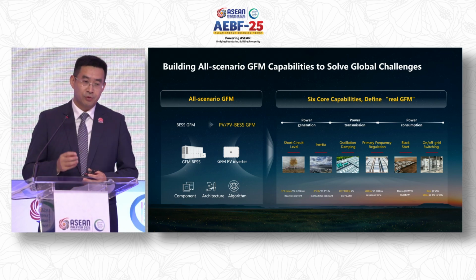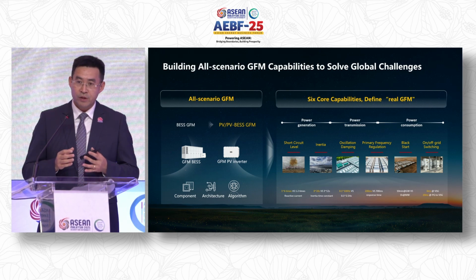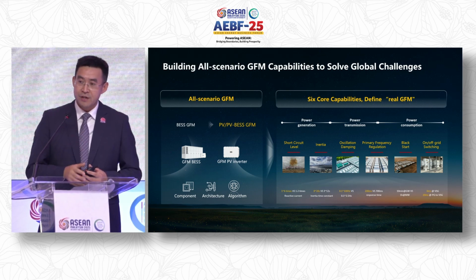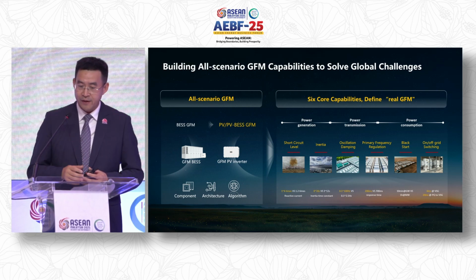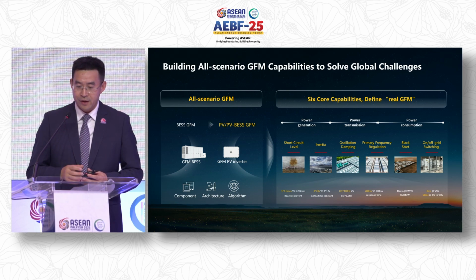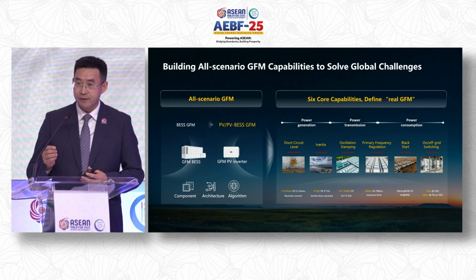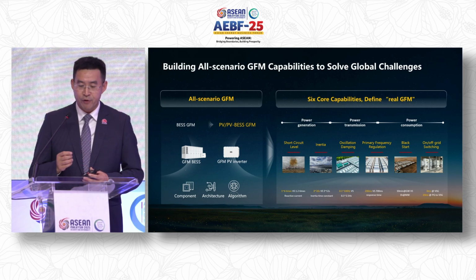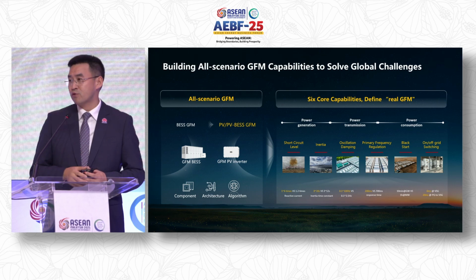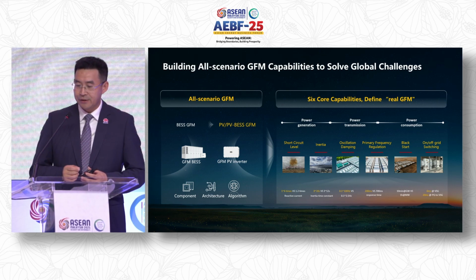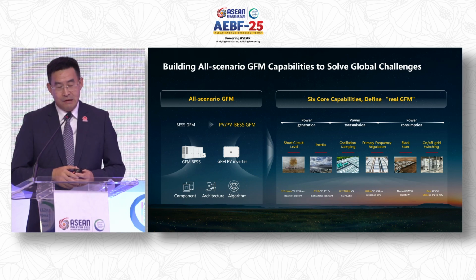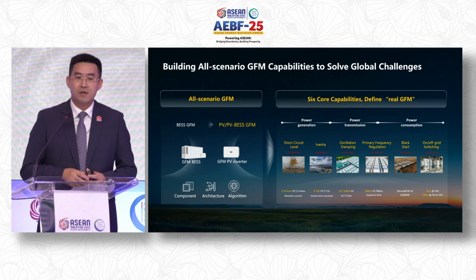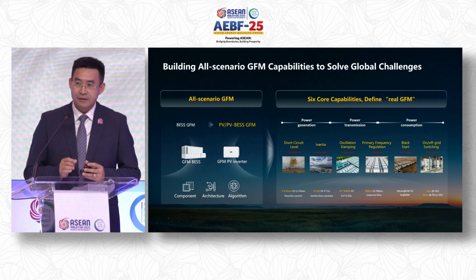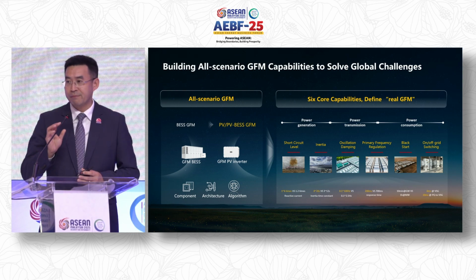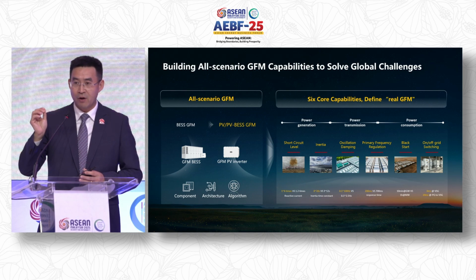Today we still want to emphasize that we define grid forming technology in 6 dimensions: first, short circuit level; second, inertia; third, oscillation damping; fourth, primary frequency regulation; fifth, black start; and sixth, on and off grid switching. These 6 dimensions are quite important for grid forming technology and standards.